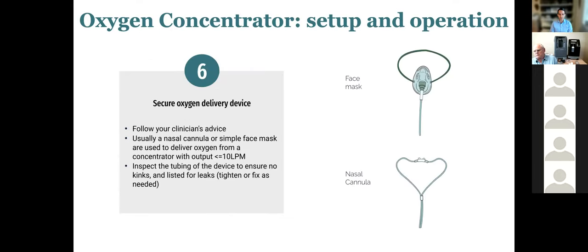And then the final step, once your oxygen concentrator is on and you've done all your tests, is to connect your oxygen delivery device. Shown here is a face mask or nasal cannula, which are two devices commonly used in patients who need 5 to 10 liters per minute or less, which is the most common amount of oxygen that most concentrators will be producing.